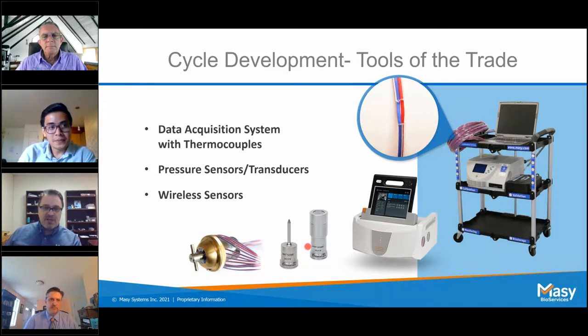They're very capable of providing a sterilizer qualification for mapping. The one other thing to keep in mind too is you will not see real-time data with these. There are also RF options which provide radio frequency data in real time, but there's a question of whether or not you're going to get through the steel walls of a sterilizer. You may not be able to get all of your sensors to read through that and get out of that environment. Also, keep in mind that when you're running with wireless data loggers, you get a lot of flexibility with thermocouples. You can get into some tight spots when you're doing load mapping. You may not have as easy a time with a wireless data logger. There are ones with flexible tips, but they're definitely not as flexible as thermocouples are. So look at what you're trying to get done and just make sure you're choosing the right tool for the job.